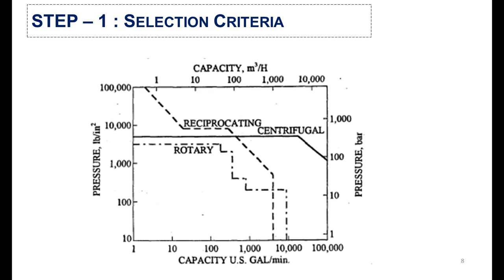In the first step, according to your requirement — whether it is to handle a higher capacity of fluid or to generate higher pressure at the downstream — you will select the pump. If your requirement is to deliver a higher fluid capacity at a medium pressure range, you will select a centrifugal pump. But if your target is to deliver fluid at high pressure with low capacity, then you will select a positive displacement pump.